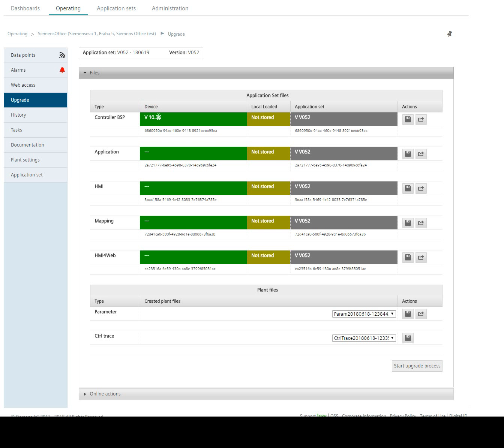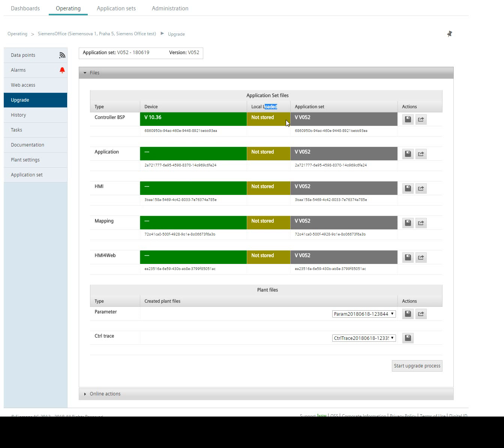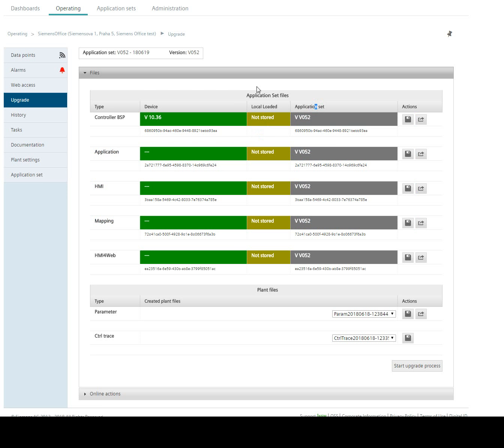Device means what is right now in your PLC and what is the hash code of the file for application, HMI mapping, and HMI for web. Local Loaded is cache memory which shows if there is some prepared file for upgrade in the cache memory. Right now all files are empty. Application set is my application set version 52 which has right now the same hash code because I have the same files in the PLC.